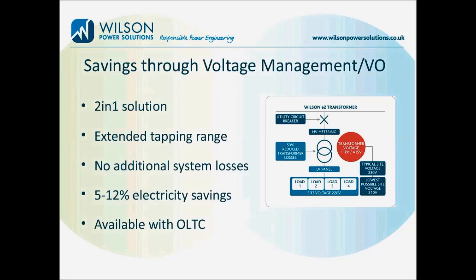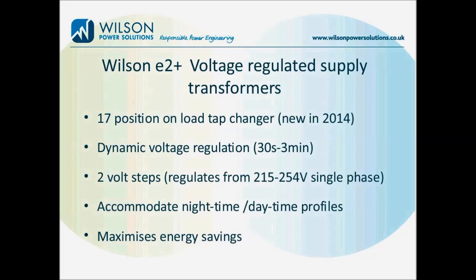But we do appreciate, of course, that site supply can fluctuate, that's incoming site supply. So we do offer a product with an automatic on-load tap changer, which has an AVR relay which allows you to fix the output voltage when necessary. Now this high voltage on-load tap changer is dynamic, and it has 17 positions, which allows you at single phase to adjust your voltage in 2 volt steps, so between 215 volts to 254 volts approximately. And many people of course talk about 220 volts as the optimum voltage to site.